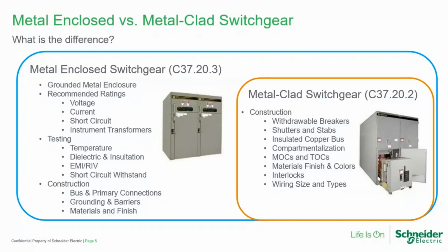The metal enclosed switchgear standard is more of a ratings and testing standard with very minimal construction requirements. It's based around giving recommended ratings so that different types of switchgear have similar rating values, so they're easier to compare to each other, as well as giving minimum test standards, both in terms of design or type tests and production testing. And then it does give some minimum construction requirements around sizing of bussing, spacing of bussing, and some materials and finishing that's required.